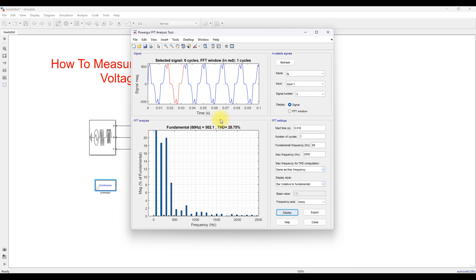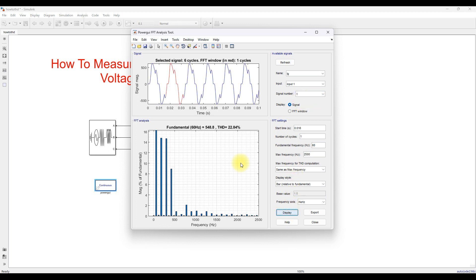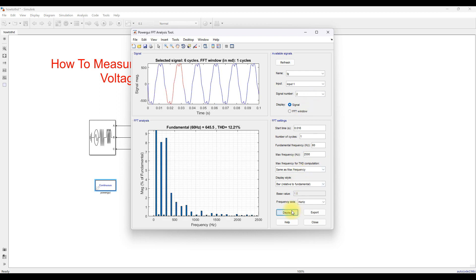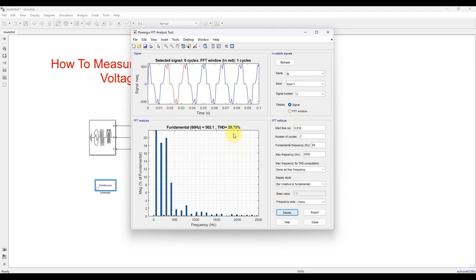Now we can see the result. The THD — total harmonic distortion — for the grid current is around 28.75%. Changing to signal one gives approximately 22.84%, the second signal is 12.21%, and the third signal is 28.75%.